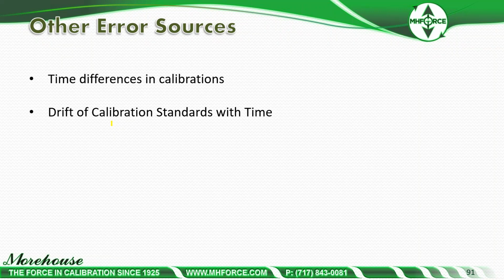It's 30 seconds. The ASTM standard just says as uniformly as possible. They could be doing 5 seconds. So 30 seconds is going to give a little bit different output than 5. And if you want to know, you should ask, how long are you holding this dwell time? Are you holding it 5 seconds? Are you just running up and down through the calibration? These are things you need to know, because you want to replicate that. Whoever's providing you with that reference information, when you're using that cell, you want to replicate it.